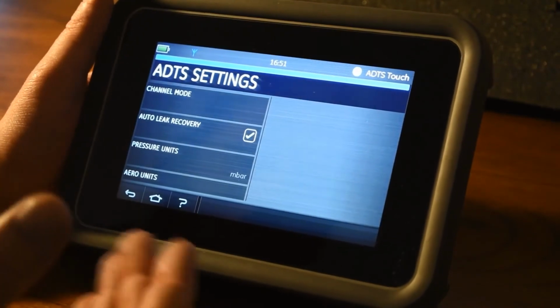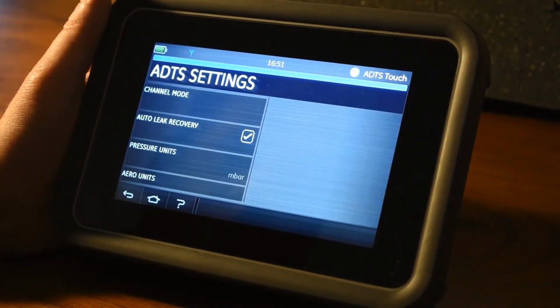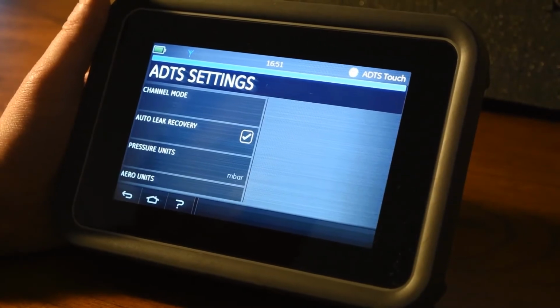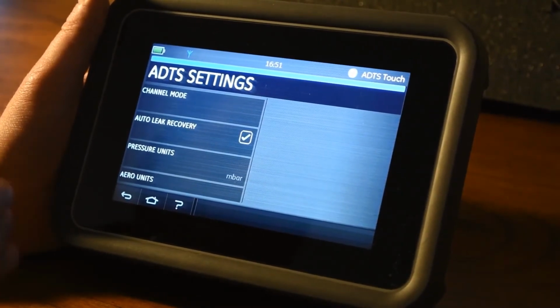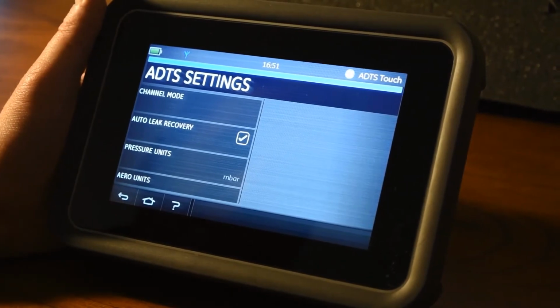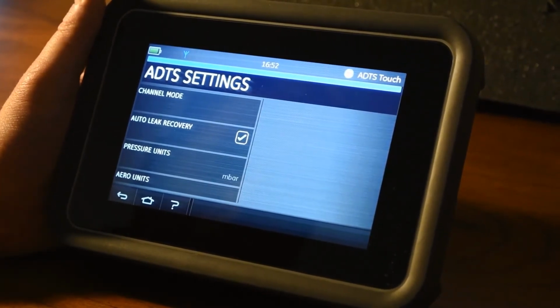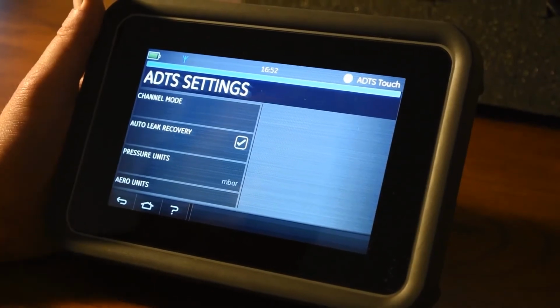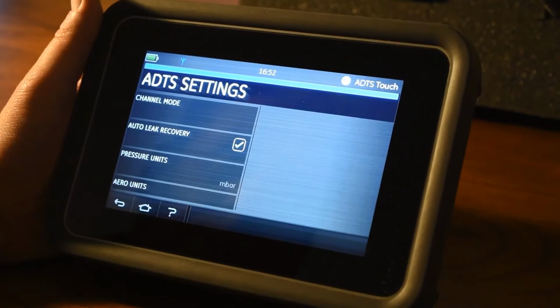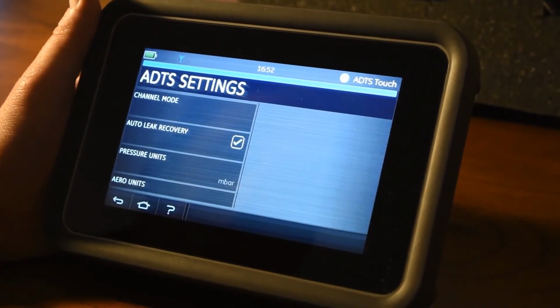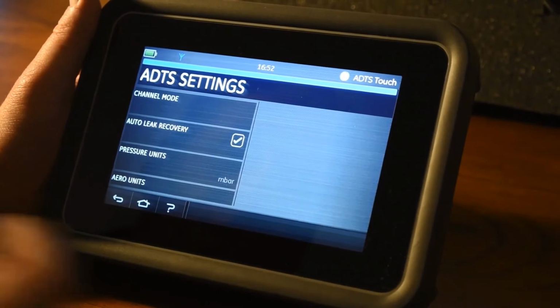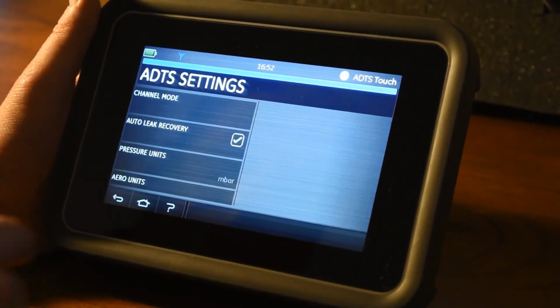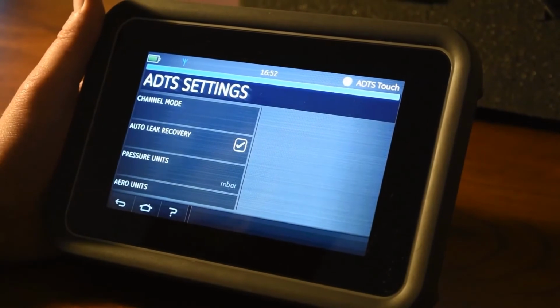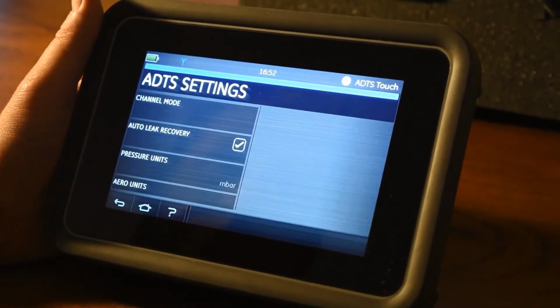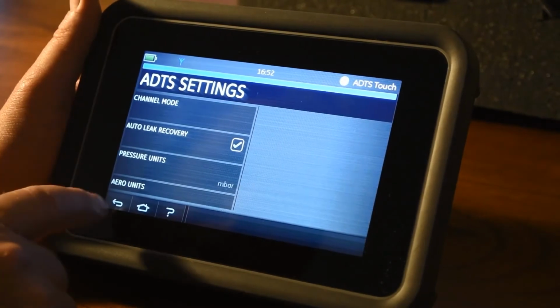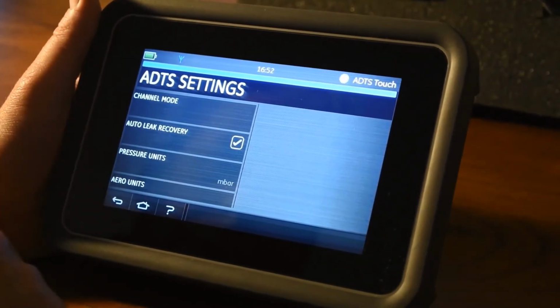If we turn from control mode to measure mode and the leak that it detects is outside of the limits we've selected for rate of climb and rate of airspeed change, so we've got a big leak, the ADTS will automatically turn the controller back on to take control, to save you from damaging any instrumentation. If it's a standard sensor and not an analog unit, it may not be an issue, but in a lot of cases there'll be analog instruments involved, so auto leak recovery is there as your safeguard.